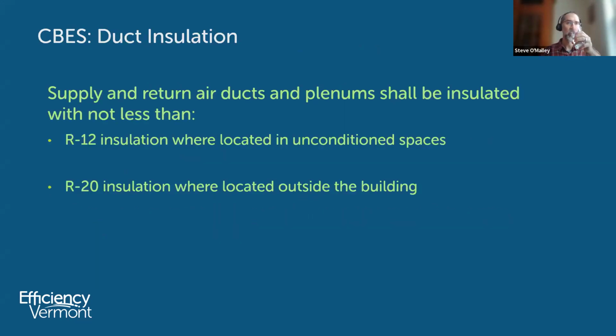Duct insulation did change the requirements. I'll just focus on CBES duct insulation because it was called out previously in terms of what you had to do with your ducts. So R12 insulation where ducts are located in unconditioned spaces, which used to be R8, and now calling for R20 insulation where located outside of the building, which in 2020 CBES was R12.